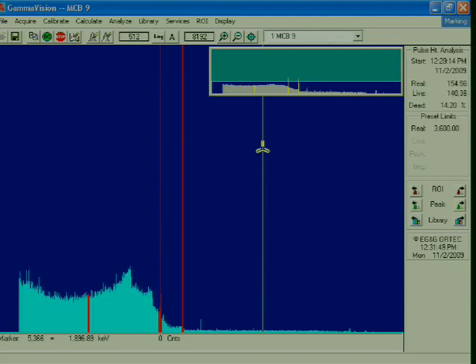It produces ionization, but the problem is the energy that electron had is not equal to the total energy the photon had when it came in. So you end up with this continuum of gamma ray events that go from 0 up to essentially the Compton edge. And you can sort of see here there are actually two Compton edges because there are two different gamma ray energies here, okay? And that's a feature of all germanium detectors, that even the largest ones today, which are 4 or 5 times as big as this one, still aren't big enough to fully contain much in the way of gamma ray energy.